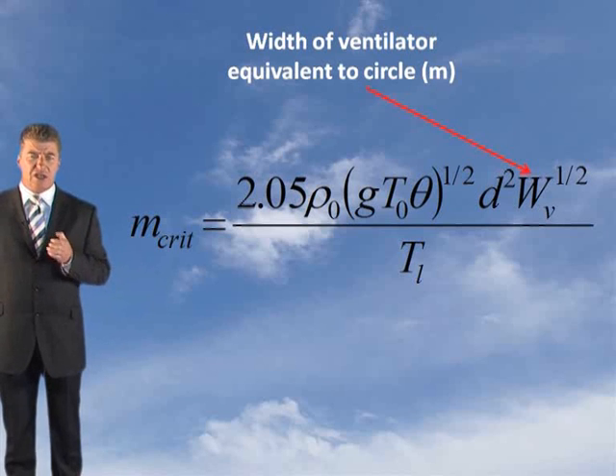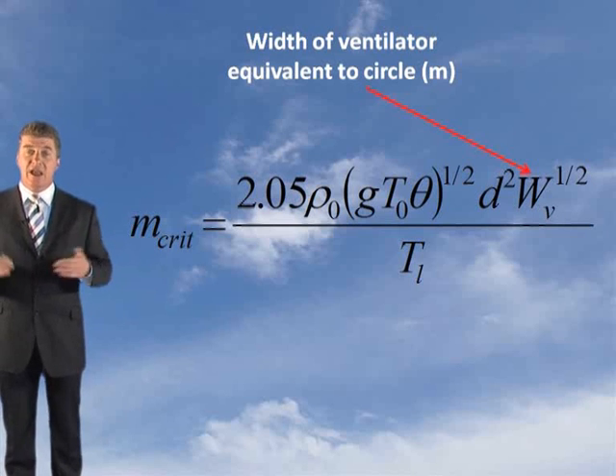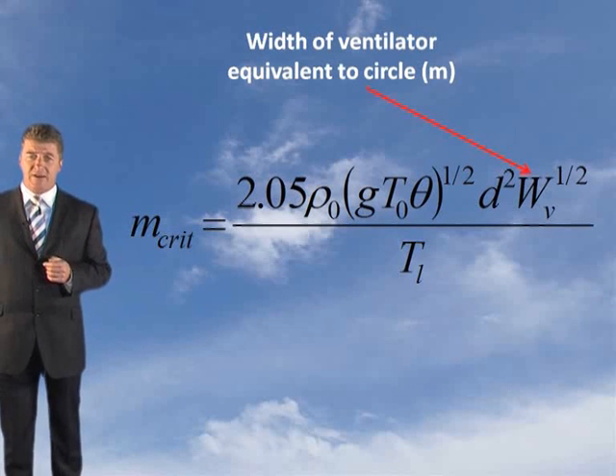WV is the width of a circular ventilator with the same area as any other vent. Because you're not sure what size vent, what shape you're going to have, you have to convert it to a circular ventilator to make this formula work. That's what WV is.